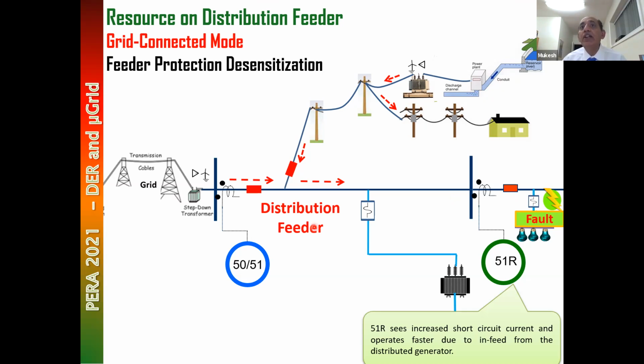Now, next point. What happens here? Some of you will be surprised actually. This was a surprise for me until I started to work. Once you connect a distributed resource here, for a fault here, if you do symmetrical component analysis, or a simple short circuit analysis for a three-phase fault, you will find the current here is lower than when this breaker is open. That means when this resource is not there, for exactly the same fault, this current will be higher, and after this distributed resource is connected, the current here will reduce.